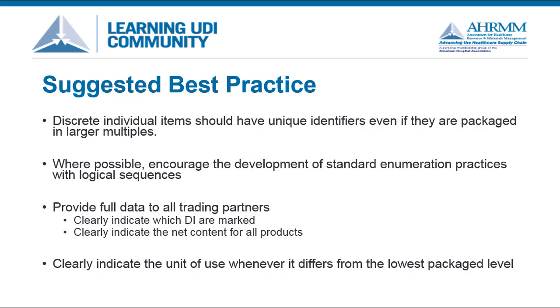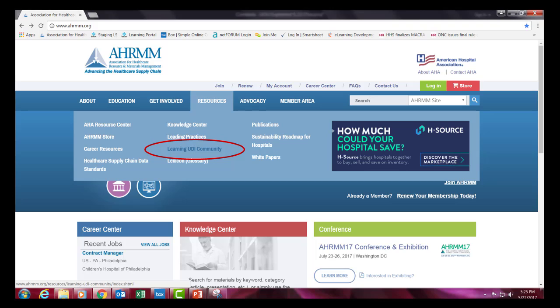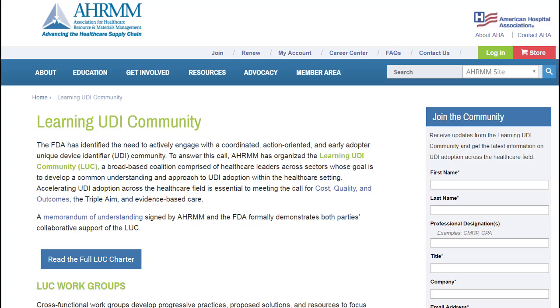Given the diversity of medical devices, this may not always be possible, so we recommend you formulate a logical sequence that works best for your organization. Once those identifiers have been created, it is important to provide the full data, including Unit of Use DI, to all trading partners. You should clearly indicate which DIs are marked and which are not, and clearly indicate the net content for all products. Finally, it is very important to clearly indicate the Unit of Use whenever it differs from the lowest packaged level. We invite you to search the Learning UDI Community Area in the AHRMM website, where we have provided slides from both the Health Industry Barcode Council and GS1 for additional information. Please refer to your respective issuing agency if you require further assistance.